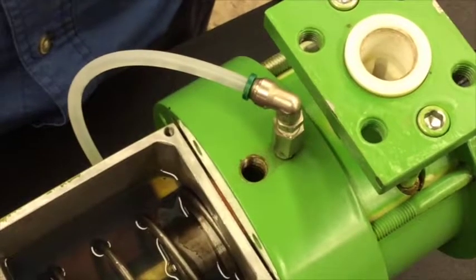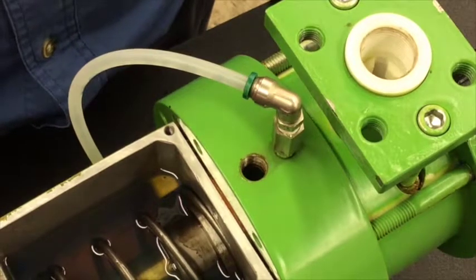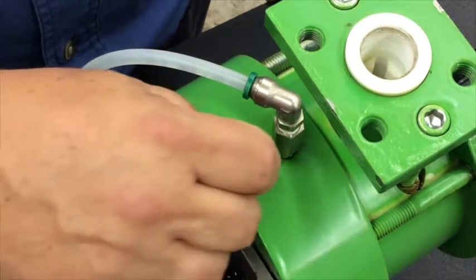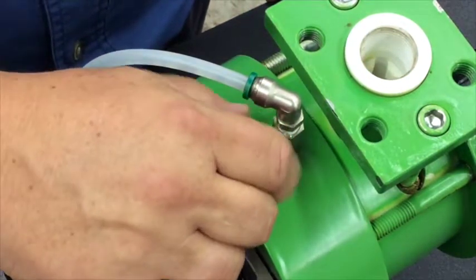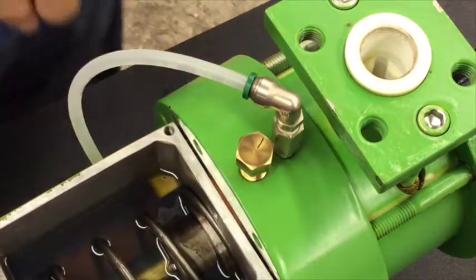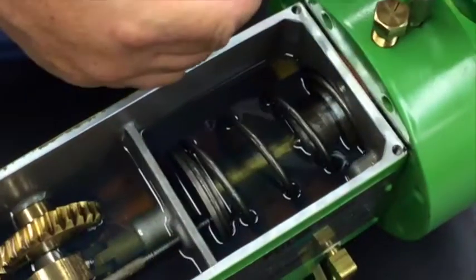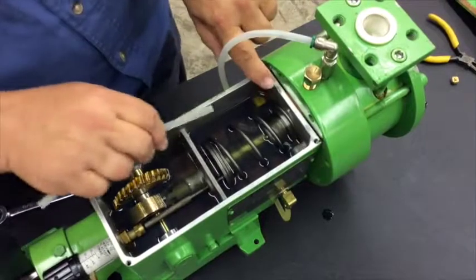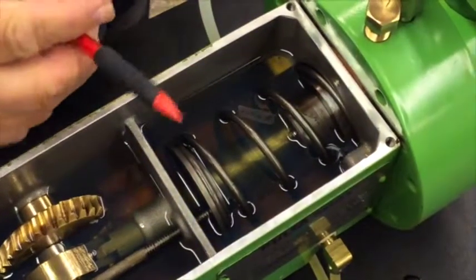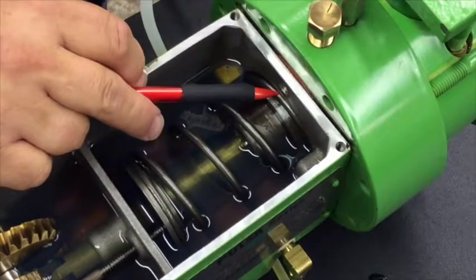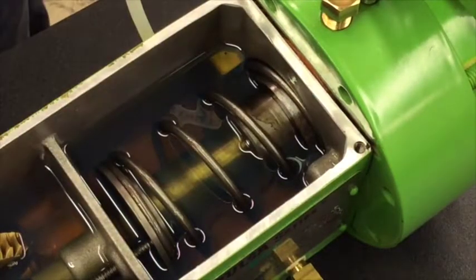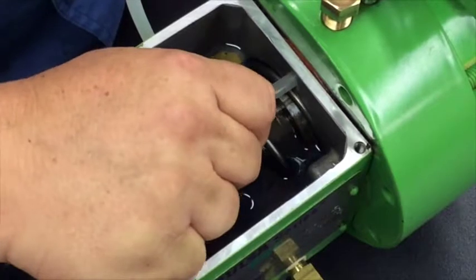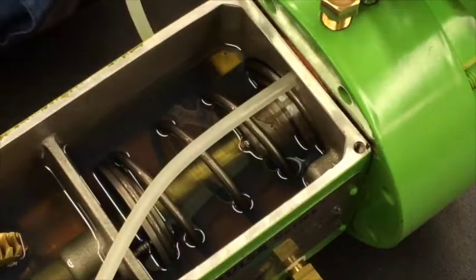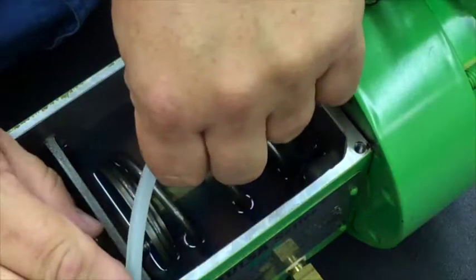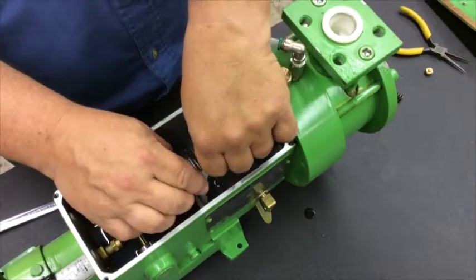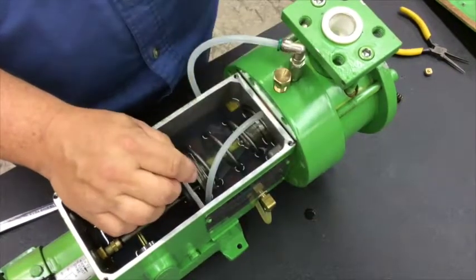I've removed the seat assembly and spring from the hydraulic bypass, and now I'm going to insert the hydraulic bypass adjustment screw back into the port and just give it a couple turns here. All right. Now I'm going to take that piece of 1/4 inch polyflow tubing and insert that into where the vent is. I'm going to take my pencil here and just point to where the vent port is. The vent port of the hydraulic bypass is located right here.